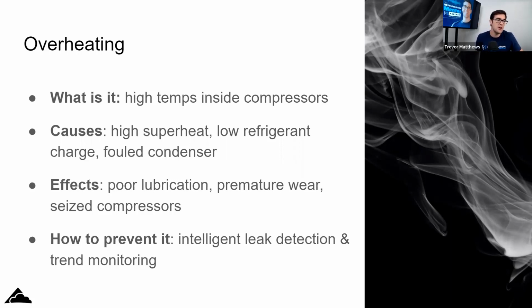One technician goes in, oh, it was overheating, let's fix this. So I cleaned the condenser. But did they fix the real problem? Maybe the condenser was dirty, but there's 3 other problems, like the superheat that Joe was talking about, or the demand cooling or liquid injection not working properly. Because they cleaned the condenser, it cools it down, but it's still not the bigger picture of what's going on.